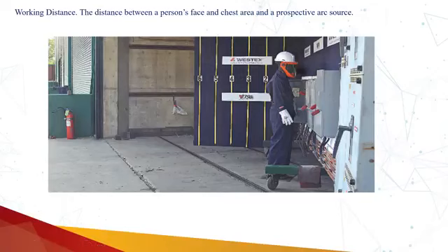So this is the point, 1.2 cal per centimeter square, which is termed as the arc flash boundary. So it reduces over the distance, and eventually it becomes 1.2 cal per centimeter square.